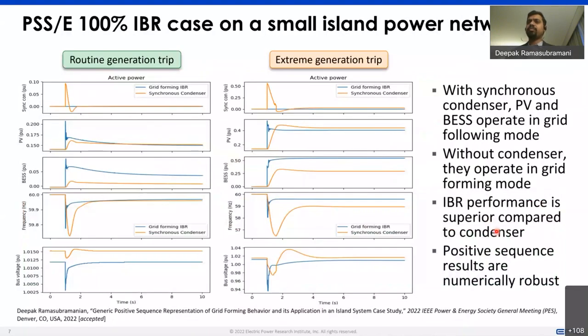And this can then be translated to the positive sequence domain also, wherein it's not just the EMT domain behavior, but the positive sequence domain behavior in software like PSSE, which is used a lot around the world for positive sequence studies. We looked at the comparison of response between a 100% inverter system with a grid forming inverter versus a 99% inverter system with a synchronous condenser. Because we are designing and tuning the controls to meet a set of performance requirements, we can see that we get superior performance with the grid forming inverter, both for a routine generation trip and for an extreme generation trip, as compared to the synchronous condenser in this positive sequence environment.